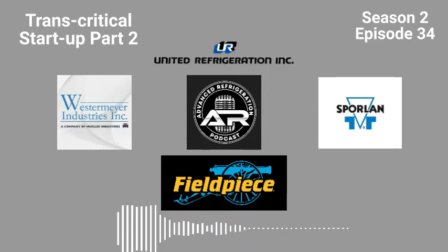I'm not turning anything on unless the whole store is piped. It all needs to be piped and functional. We've hardly got to do any functionality tests, but we're pretty confident in the actual case sensors. These particular cases — every evaporator outlet temp sensor, there's three of them per Hussmann case, but they're all different colors and they're home-run all the way through, so they all look to be landed right.